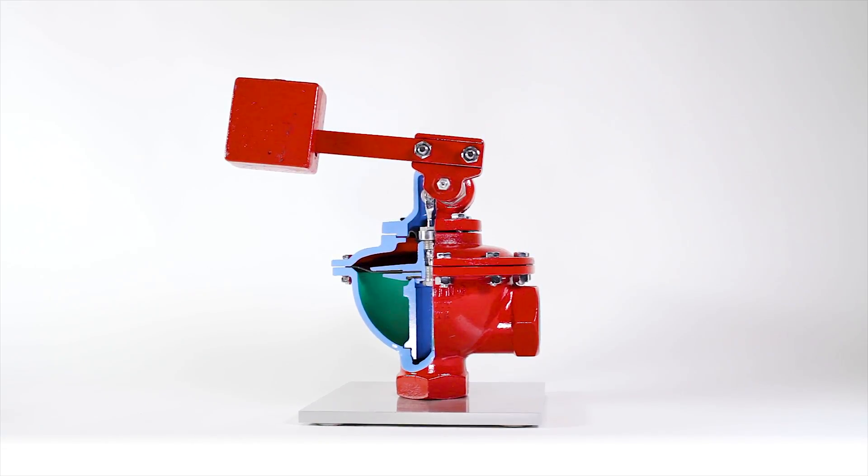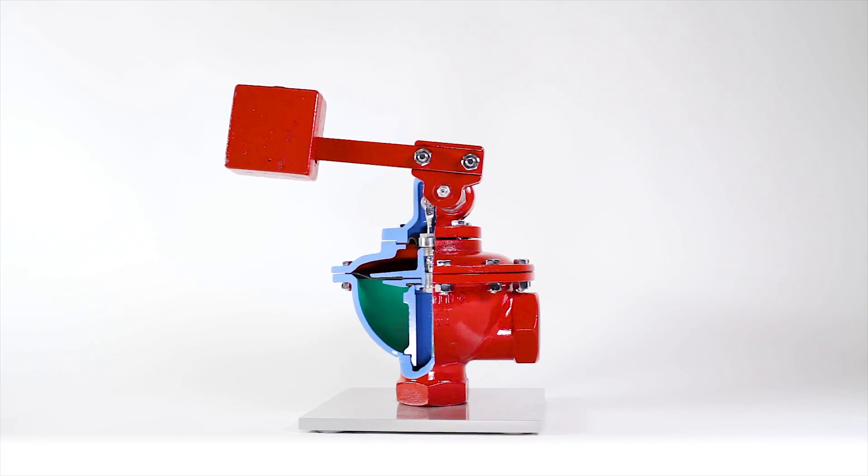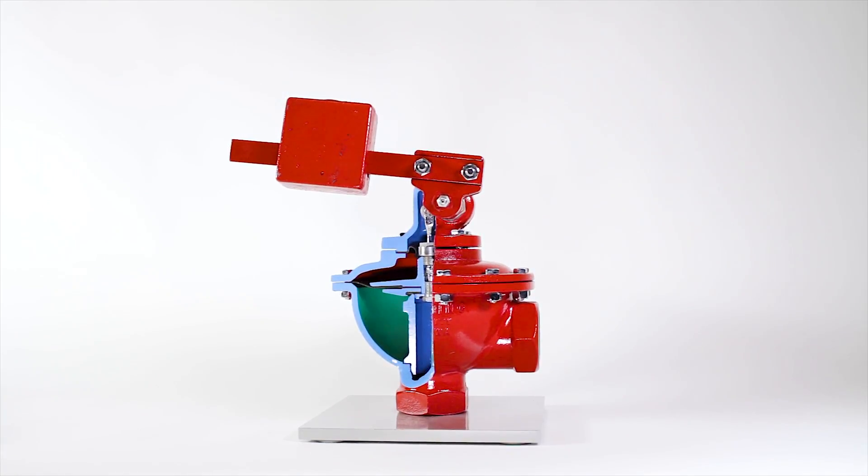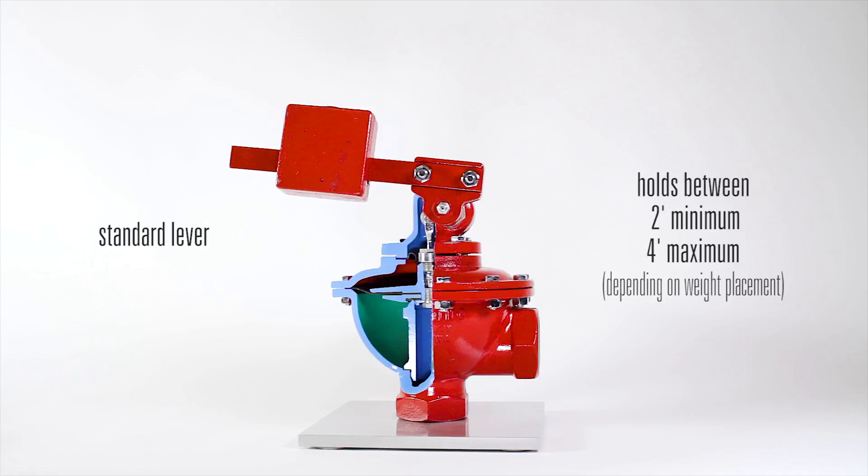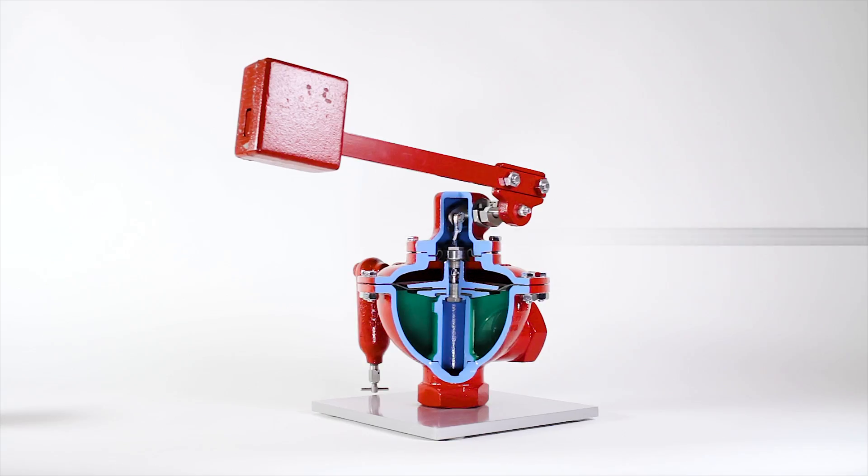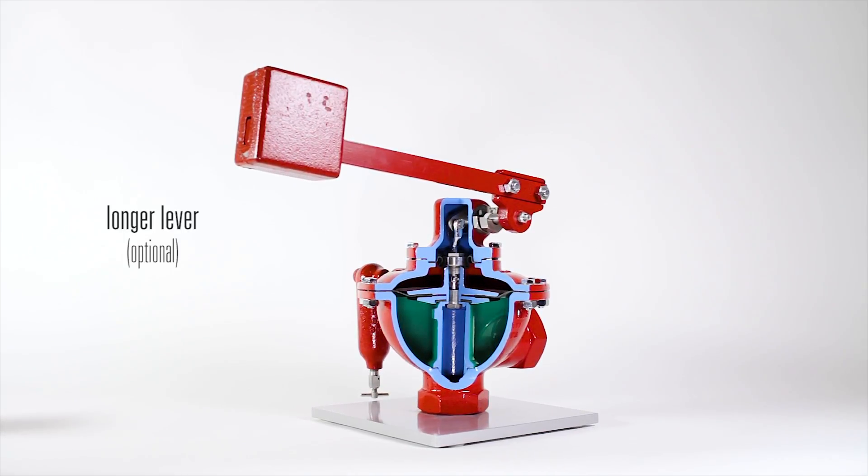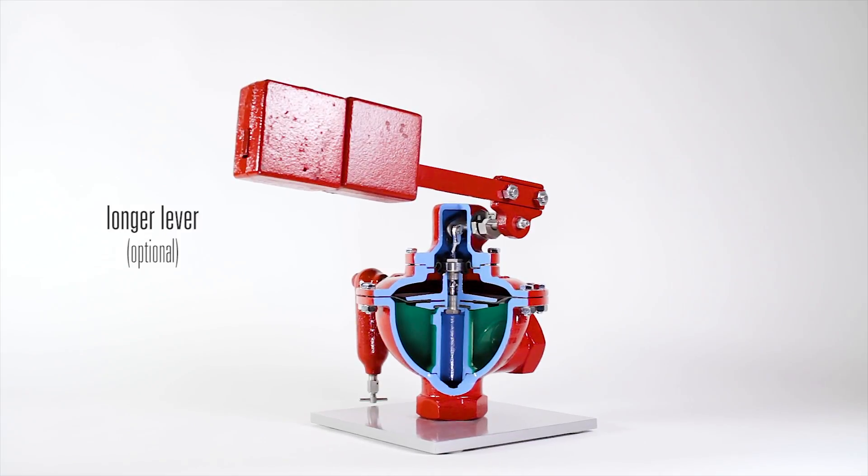The height of the water column can be field adjusted by moving the weight on the attached lever in or out. The standard lever is designed to hold between two and four feet of liquid. Higher liquid levels can be achieved with an optional longer lever and an additional weight.